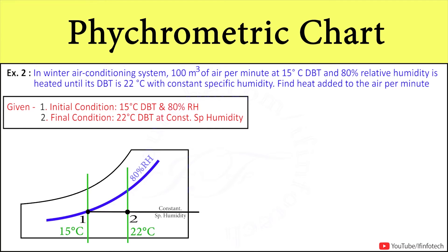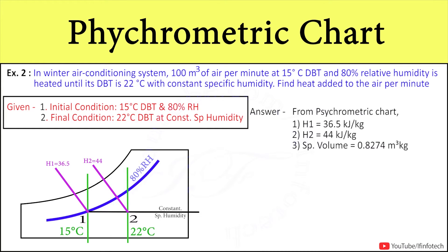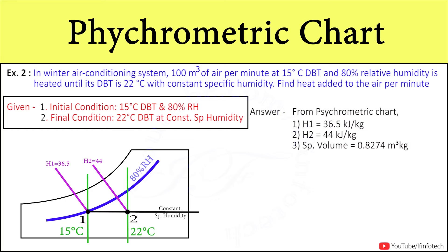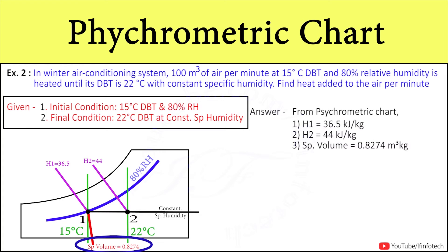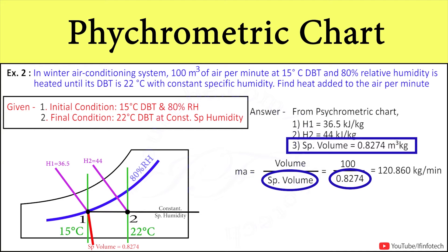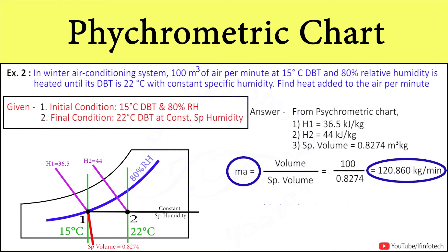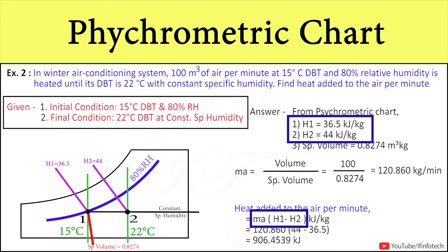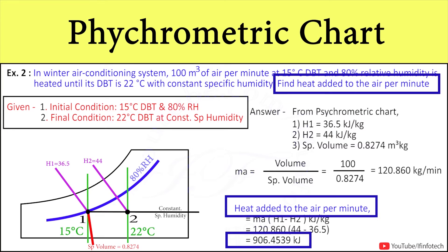From the specific enthalpy lines, h1 is approximately 36.5 kJ/kg for initial condition and h2 is 44 kJ/kg for the final condition at 22°C DBT. The specific volume line for the initial condition gives 0.8274 m³/kg. Using the volume of air (100 m³/min) and specific volume (0.8274 m³/kg), we calculate the mass of air, then use the enthalpy difference to get heat added as 906.45 kJ per minute.